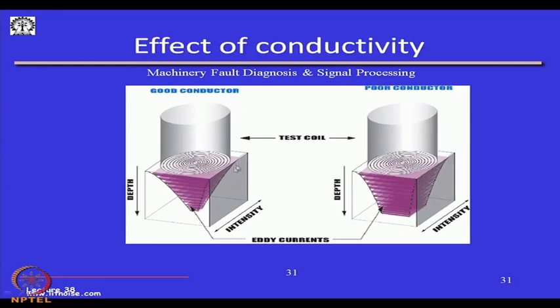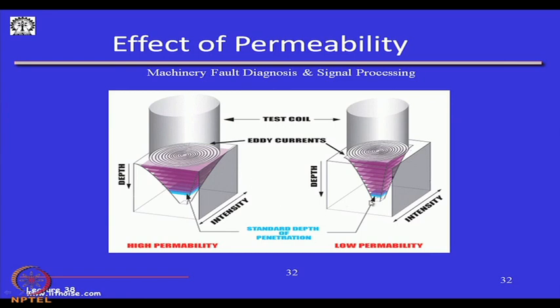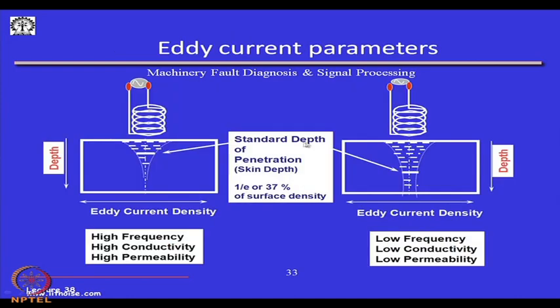There is an effect of frequency: if the primary coil excitation frequency is high, the penetration depth is low; if the frequency is low, the penetration depth is high. The conductivity of the material also plays a role — if it is a poor conductor, the eddy current intensity is different than in a good conductor. Similarly, low permeability and high permeability affect the depth and intensity of eddy currents differently.